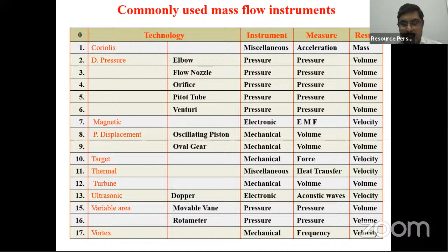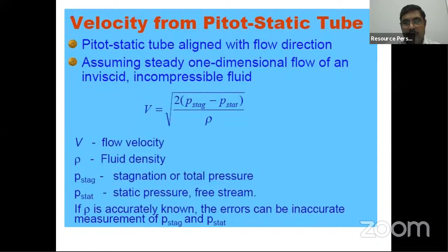So we have seen that by using a pitot static probe, one can get the velocity. Once you know the velocity, you can get the flow rate by multiplying by the area of cross section. So pi d square by 4 into V will give you the flow rate in meter cube per second. This is a very simple thing. And you can see here how it can be measured using this kind of manometer. You can measure the value of H, and with the value of H, you can measure the flow rate.